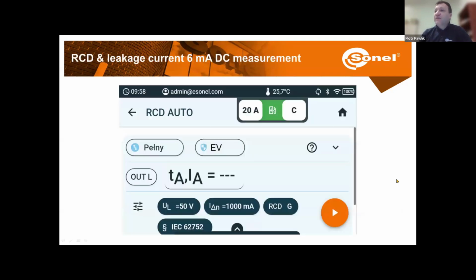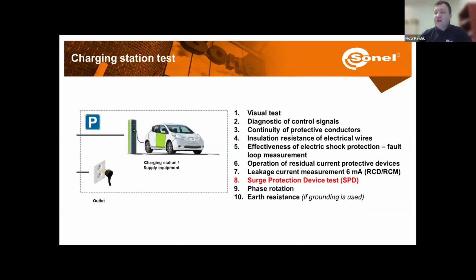Okay, so we can check it on the meters. We can select what type of RCDs we are having. We can check disconnection times for different values of nominal currents, different multiplication of nominal currents, as well as the disconnection current. And at the end, we will have all the results on the meter.